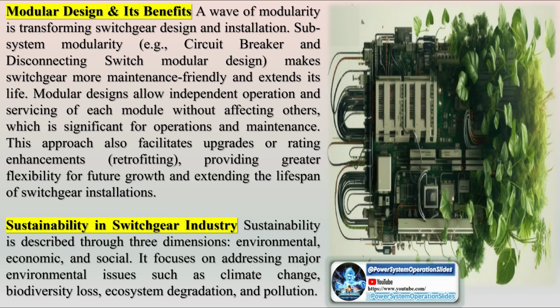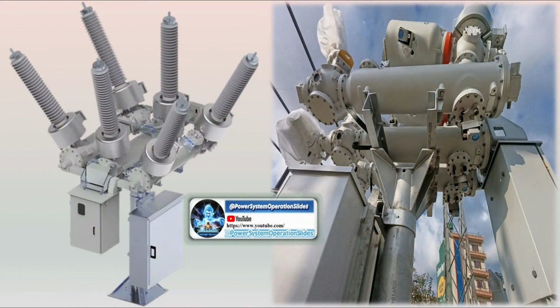Hybrid gas-insulated switchgear. HGIS offers significant environmental benefits by reducing SF6 gas consumption compared to traditional SF6 gas-insulated switchgear at the same voltage level. Here's a more detailed look at these benefits. Reduced SF6 gas consumption. HGIS can save up to 2/3 of SF6 gas consumption compared to conventional GIS. This reduction is achieved by combining gas-insulated components with solid insulated busbars, which eliminates the need for SF6 in certain parts of the switchgear.